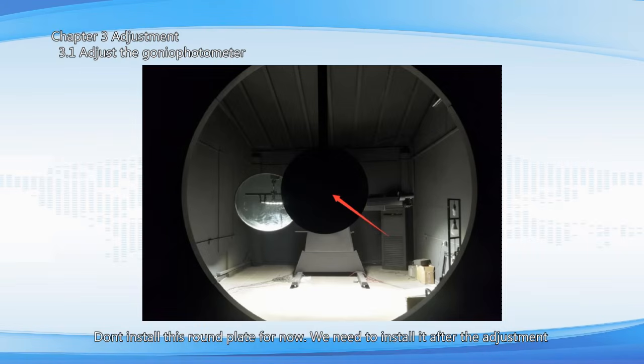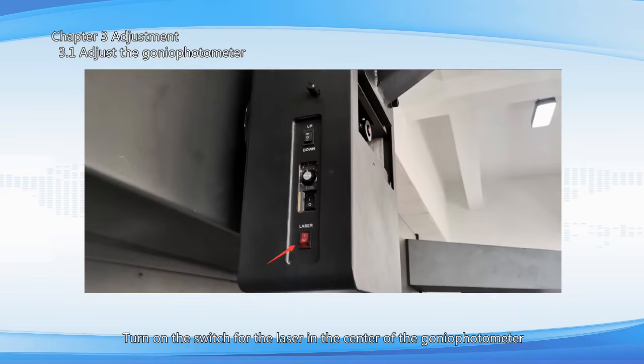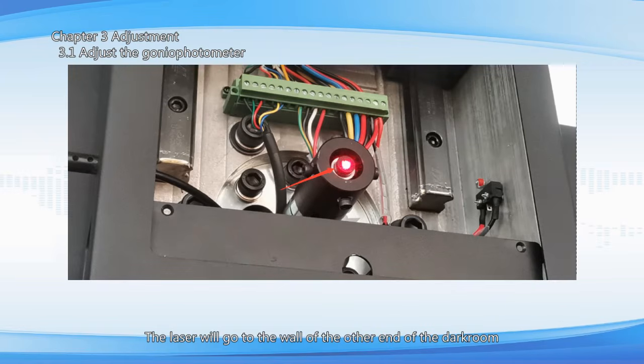Chapter 3. Adjustment. Adjust the goniophotometer. Don't install this round plate for now. We need to install it after the adjustment. Connect the power cord for the goniophotometer. Turn on the switch for the laser in the center of the goniophotometer. The laser will go to the wall of the other end of the darkroom.